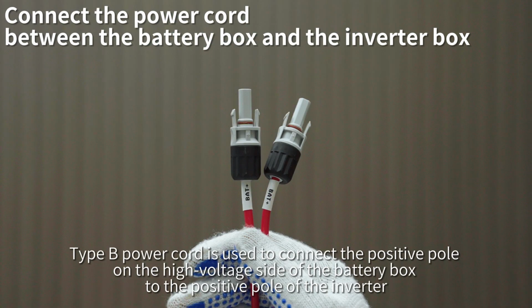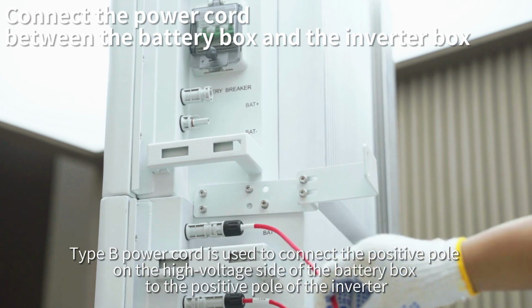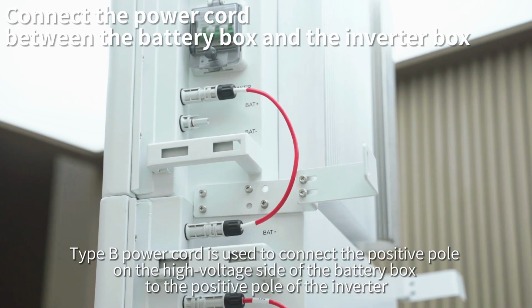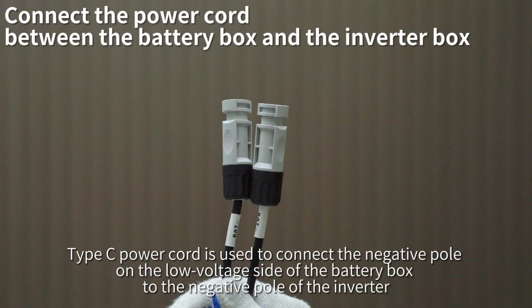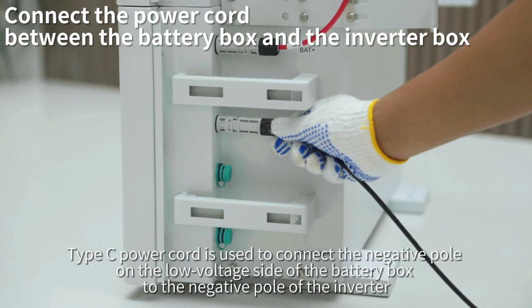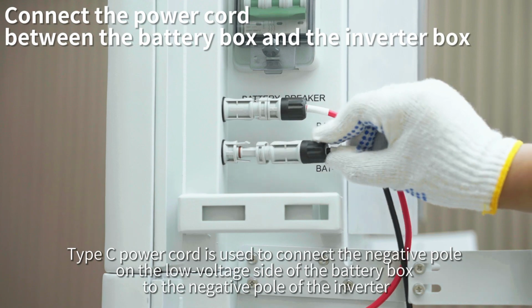Type B power cord is used to connect the positive pole on the high voltage side of the battery box to the positive pole of the inverter. Type C power cord is used to connect the negative pole on the low voltage side of the battery box to the negative pole of the inverter.